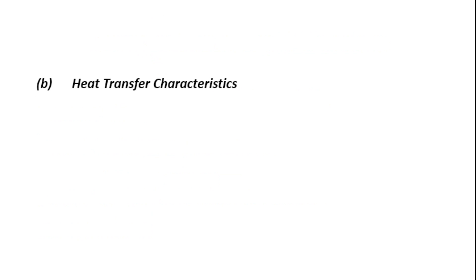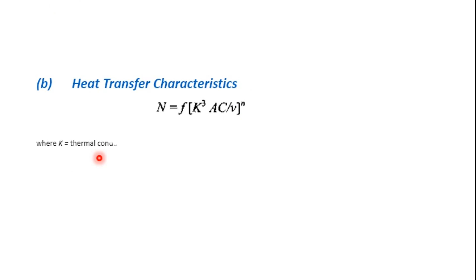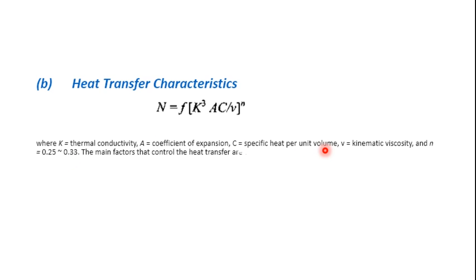Then we have heat transfer characteristics. In equipment filled with liquid dielectric — like transformers, cables, and circuit breakers — heat is transferred mainly by natural convection. Under natural atmospheric conditions, the cooling convection is given by: N = f · [k³ · a · c / v]^n, where k is thermal conductivity, a is the coefficient of expansion, c is specific heat per unit volume, v is kinematic viscosity, and n varies from 0.25 to 0.33. The main factors controlling heat transfer are thermal conductivity and viscosity.